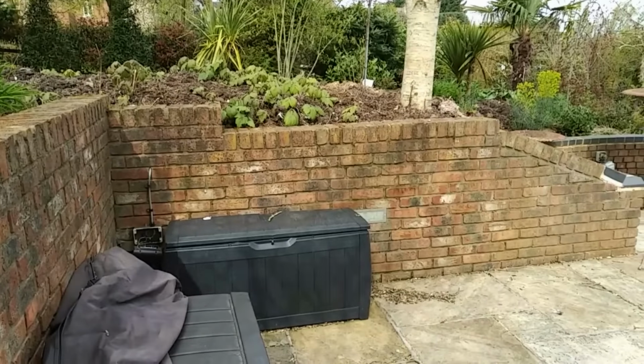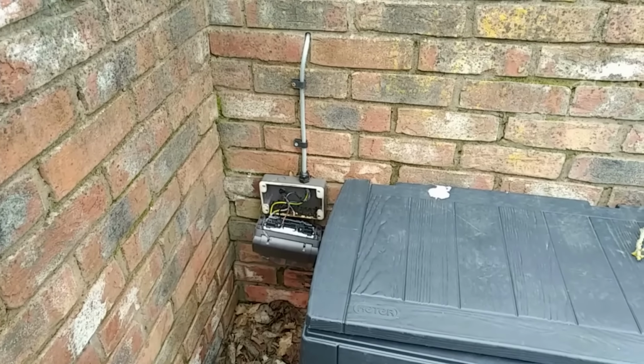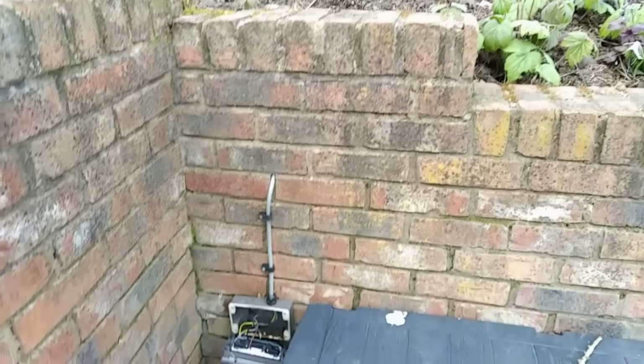What we're going to have to do now, this first socket in the chain, obviously that's had it. And can't get to where the junction is, there's no junction going through it. We're going to whisker that off, stick some Wago connectors on the end, properly seal it, and that's that out of the way. This socket here I think is just about serviceable, might need just a bit of tidying up on it. This one down here, the only thing I can think of is that we perhaps put a junction there and a new section of armoured cable coming off it, although getting through this wall is going to be a pain in the arse.